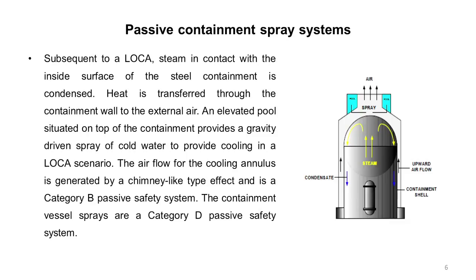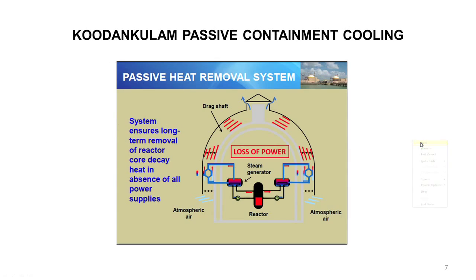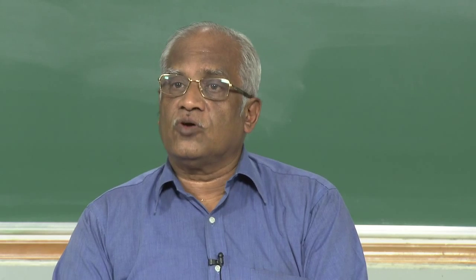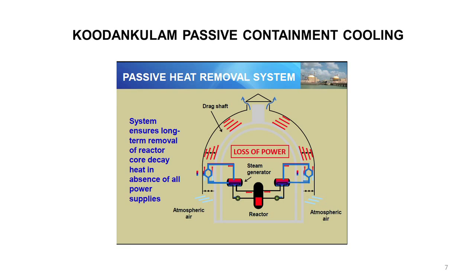This sort of system has been used in many pressurized water reactors. Here I show you the passive containment cooling system adopted in the Koodankulam reactor, which is in operation in Tamil Nadu. There is a lot of annular space in the actual building, so atmospheric air enters, picks up heat from the containment, and goes out. Even when there is a power failure, you are able to do this by natural convection — you are not dependent on any electrical or mechanical power.